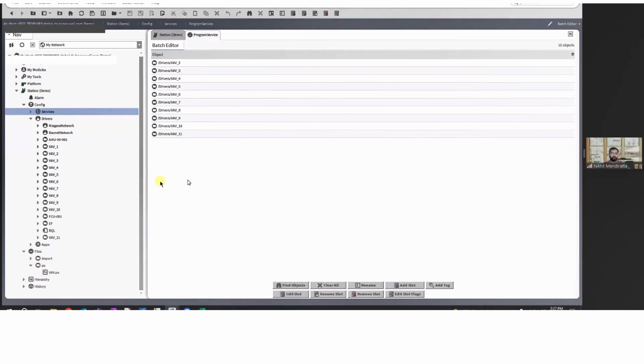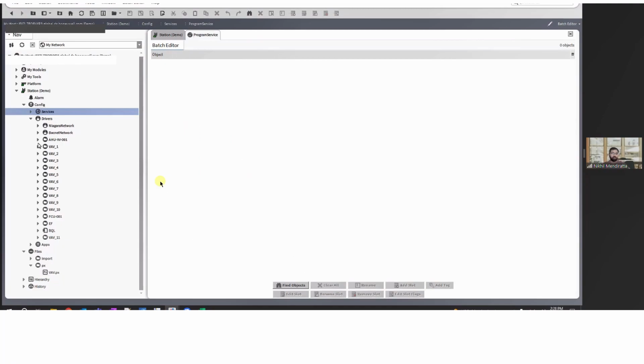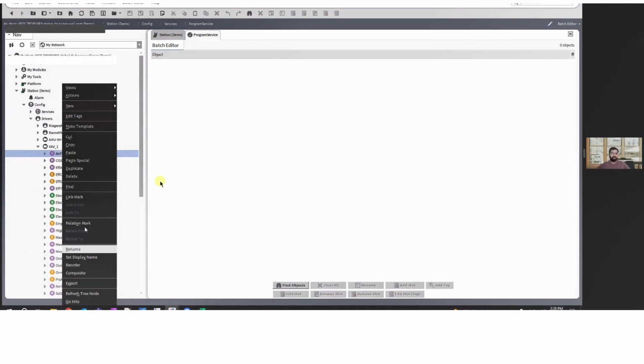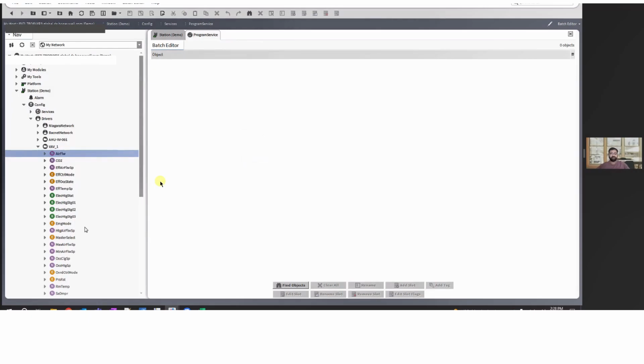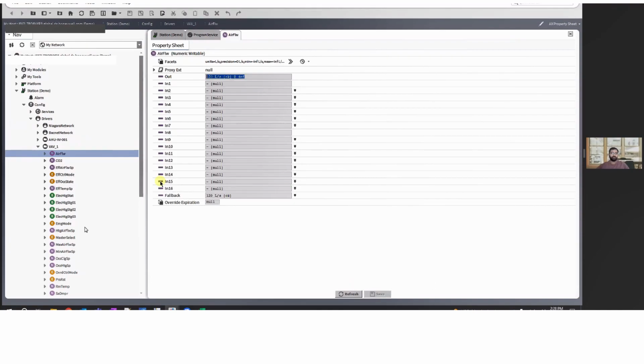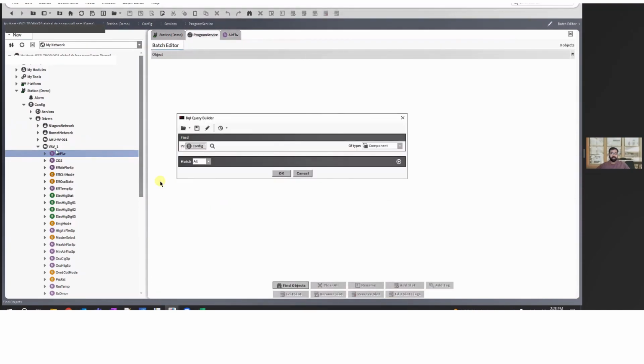Sure. So if we go to program service, I'll clear all. Let's take an example of airflow. We are going to change the unit to CFM — earlier it was liter per second. If I go to program service, I'll do find objects, keep it to config, and choose the control point.